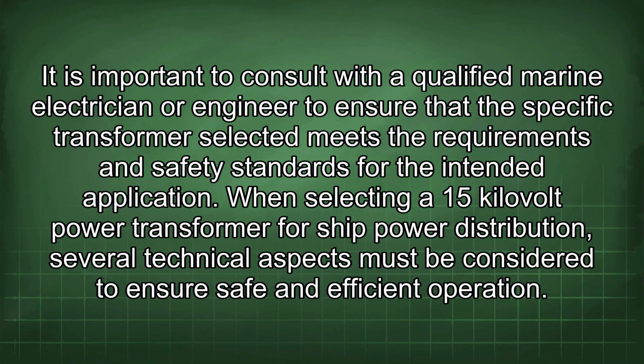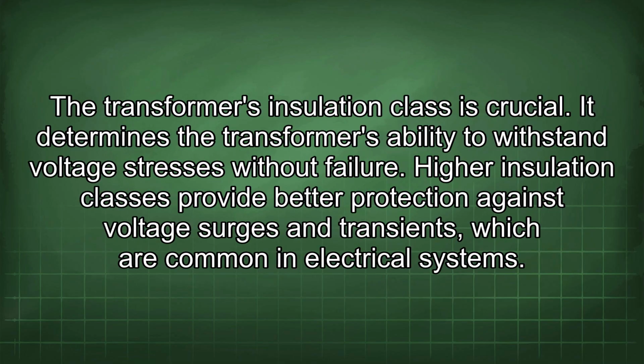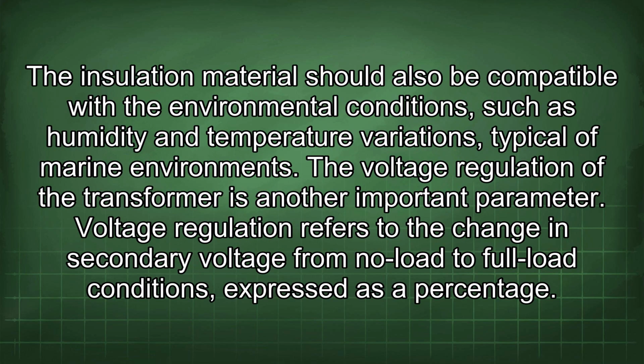When selecting a 15 kilovolt power transformer for ship power distribution, several technical aspects must be considered to ensure safe and efficient operation. The transformer's insulation class is crucial. It determines the transformer's ability to withstand voltage stresses without failure. Higher insulation classes provide better protection against voltage surges and transients, which are common in electrical systems. The insulation material should also be compatible with the environmental conditions, such as humidity and temperature variations typical of marine environments.